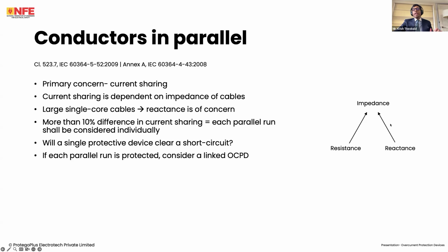The primary concern here is: is each run going to be sharing the same amount of current? And I'll show you why. Obviously, the ratio of current sharing is very dependent on the impedance of the cables. This is not just the length of runs, but also the spacing, and I'll show you what I mean. When we have larger single core cables, for example 630 mm² conductors per phase, more than the resistance, the reactance is of concern here. When we have more than a 10% difference in current sharing, we need to consider each parallel run individually, not only for overload protection, but for short circuit protection. And this is a question of, will a single protective device be able to clear a short circuit? I'll show you what I mean. And if we decide that each parallel run has to be protected, the best option is the linked OCPD, and I'll show you what I mean as well.